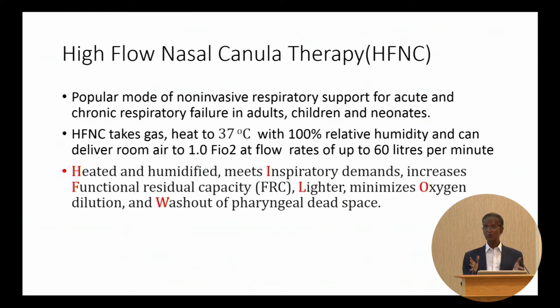So what does it do? You have a system, an equipment that delivers the high flow. The device takes the gas, heats it up to body temperature of 37 degrees, and provides almost 100% humidity, and then you can deliver room air, you can deliver 40% oxygen, you can even deliver 100% oxygen, and the flow can go up to 60 liters per minute.